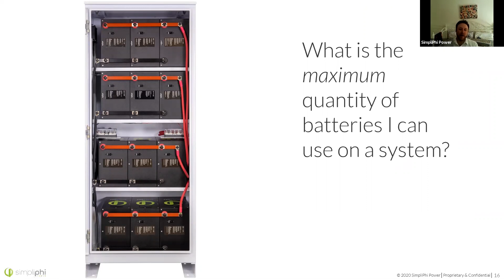All right, same vein, what is the maximum quantity of batteries I can use on the system? This one's a bit easier to follow. So typically, first and foremost, I'd say there is no limit to how many of our standard PHI batteries can be put into parallel. Load calculation, I'll still always say that's key. That's going to be your number one starting point here. You don't want to just size because you can. But again, the standard battery has no limit to how many you can parallel.